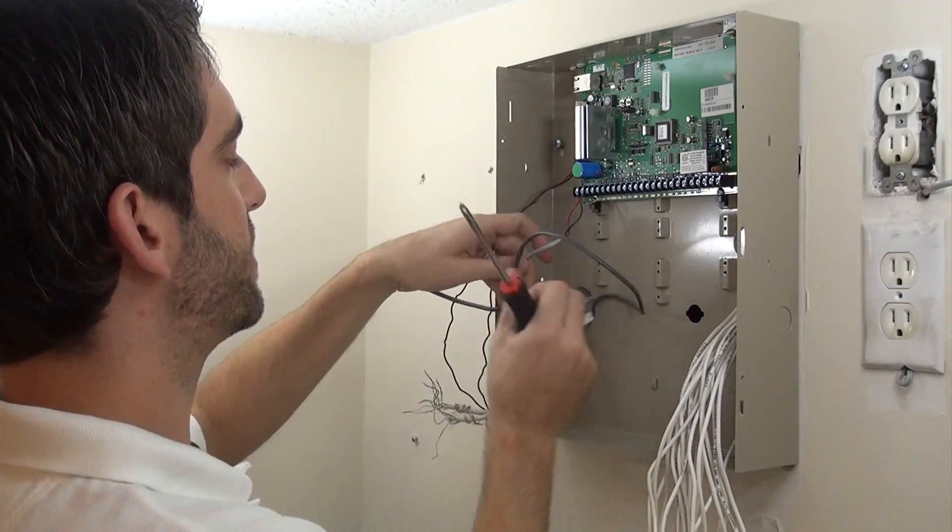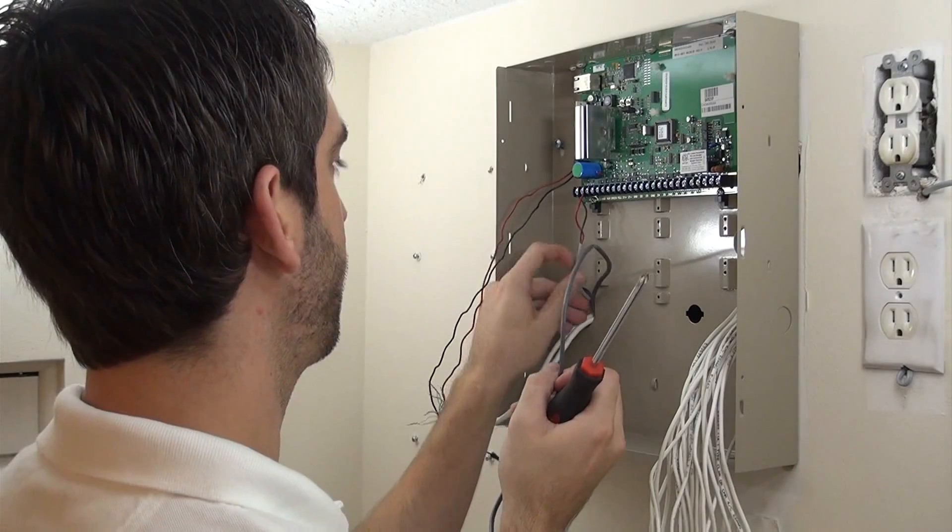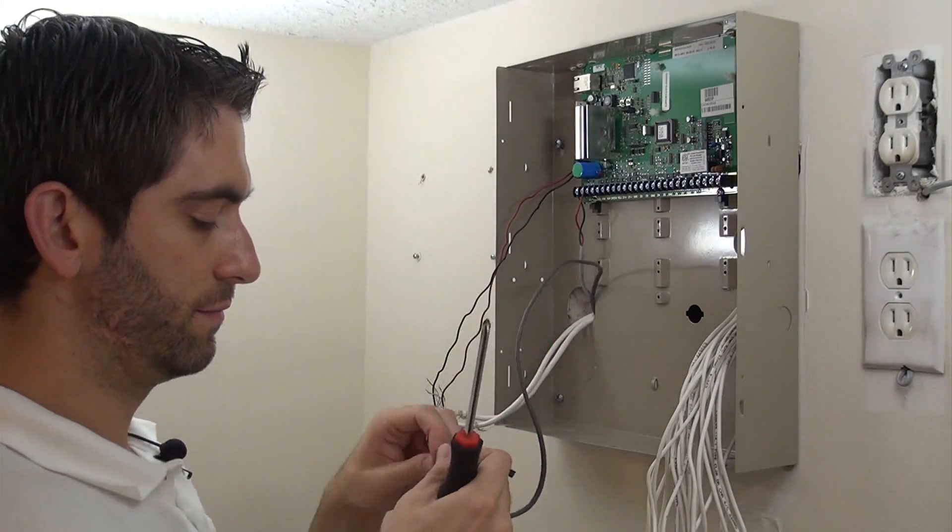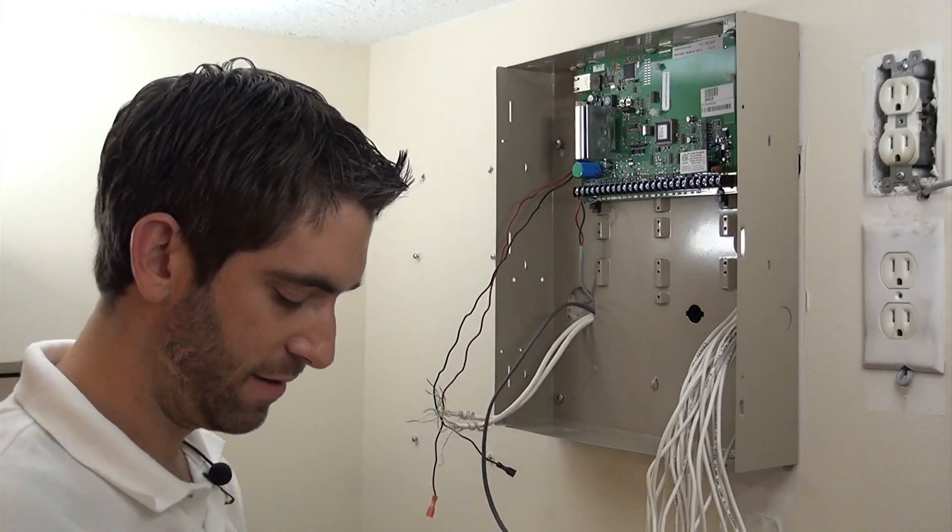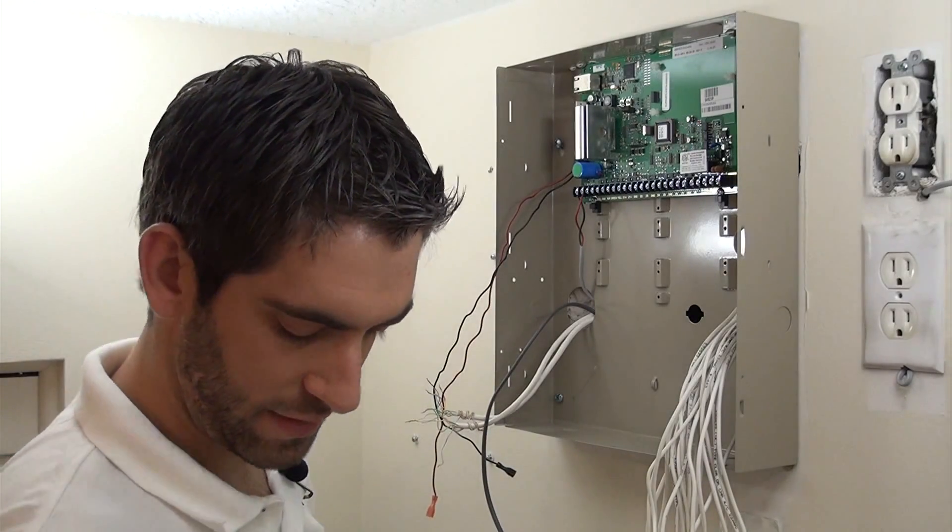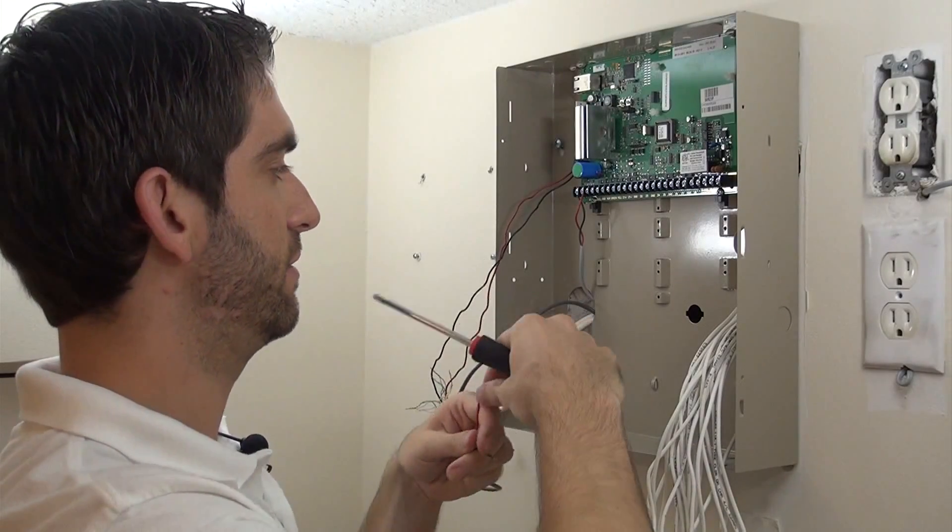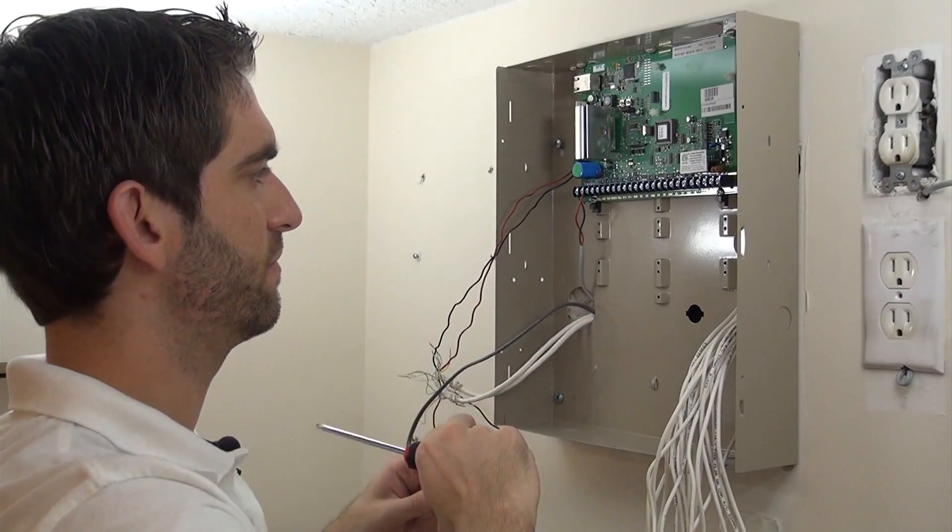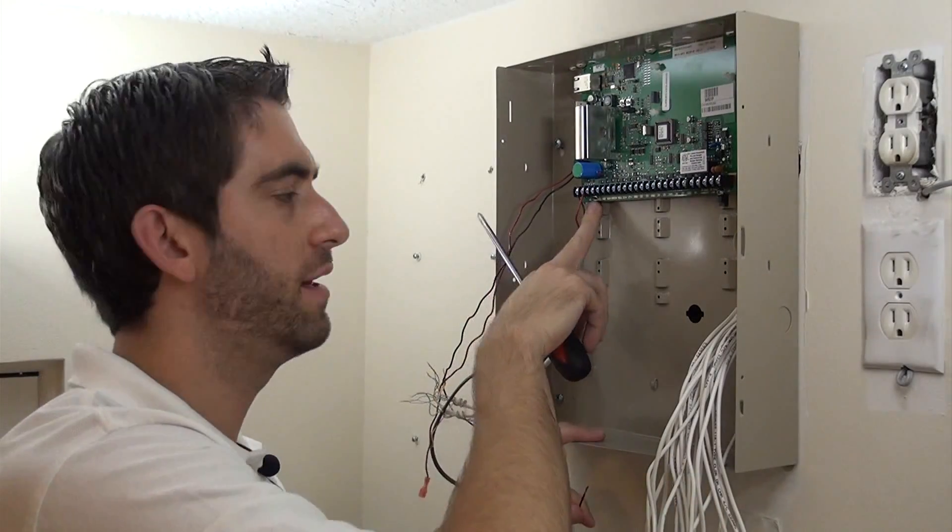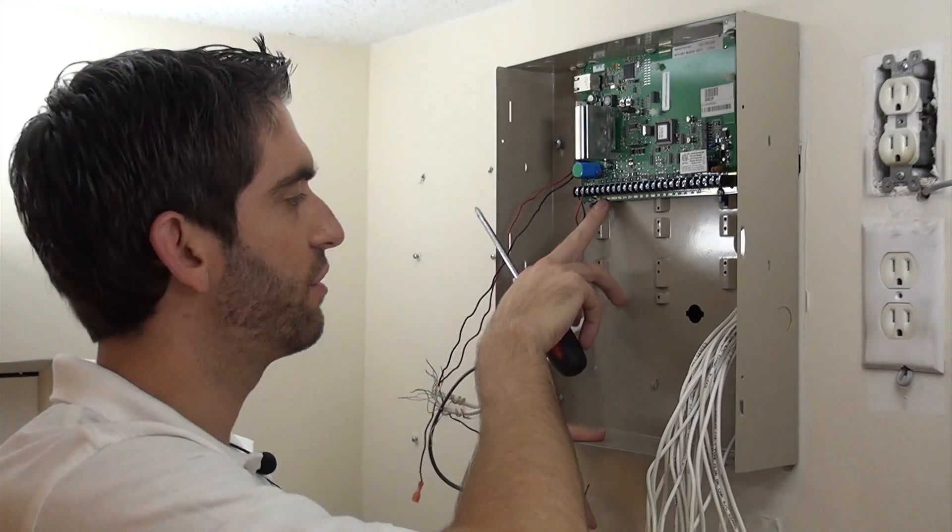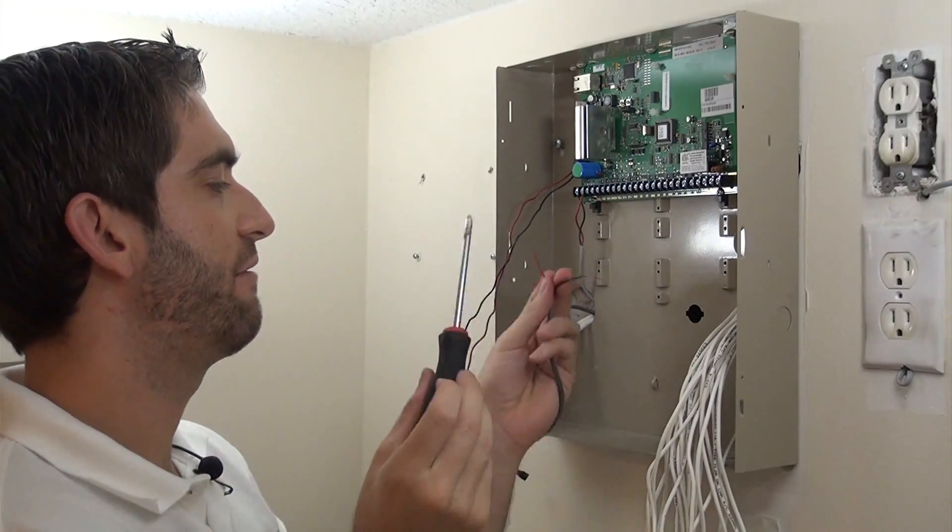Next one we're going to connect is our siren wire. For our siren, we also have black and red. This time polarity does matter though. Twist our ends. And so we've got terminal screw three is bell, four is ground. Ground is our negative power terminal, and this bell is our positive siren output.